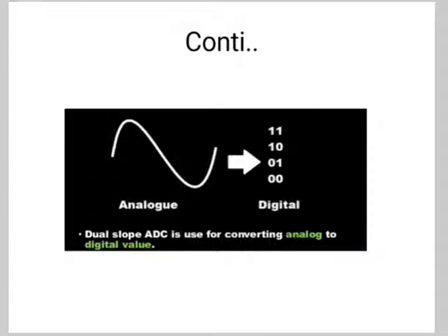When a dual slope A to D converter is used for a digital multimeter, the counter may be decade rather than binary, and the segment and digit drivers may be contained in the chip. When the converter is to be interfaced to a microprocessor, and many high performance digital voltmeters use a microprocessor for data manipulation, the counters employed are binary.